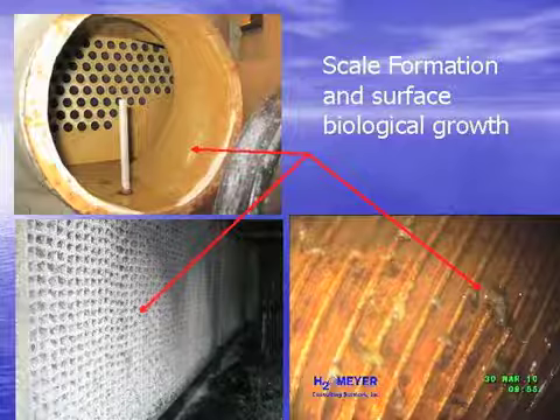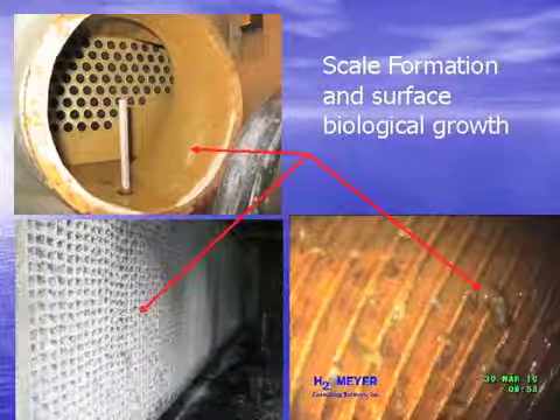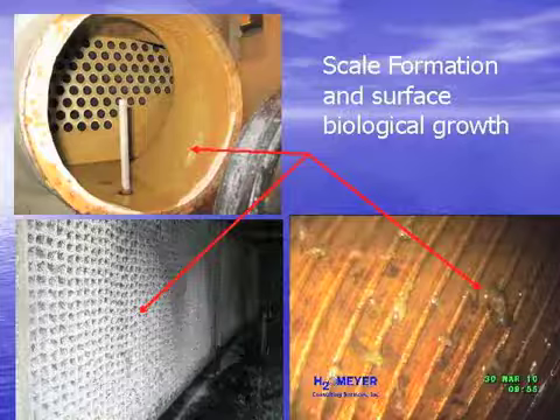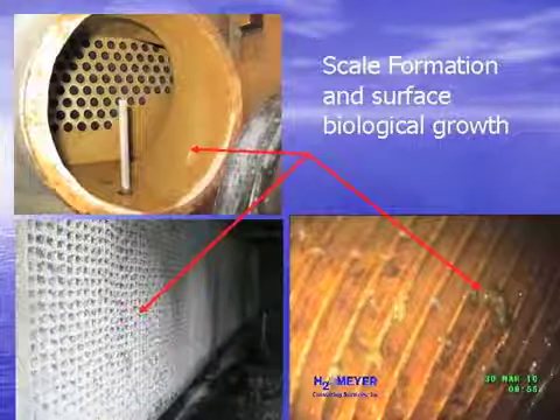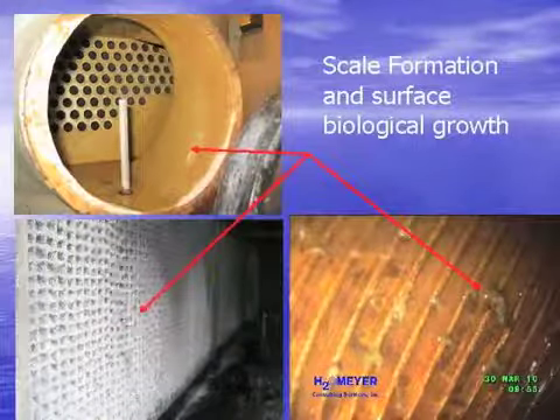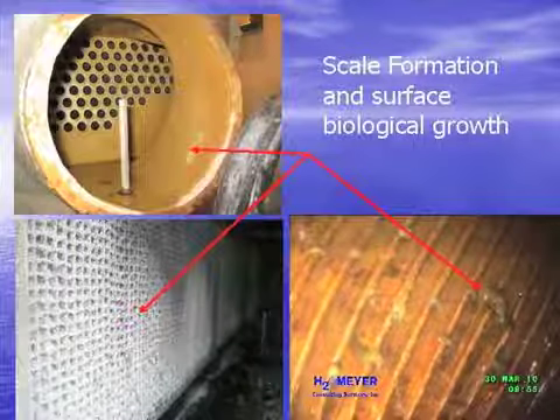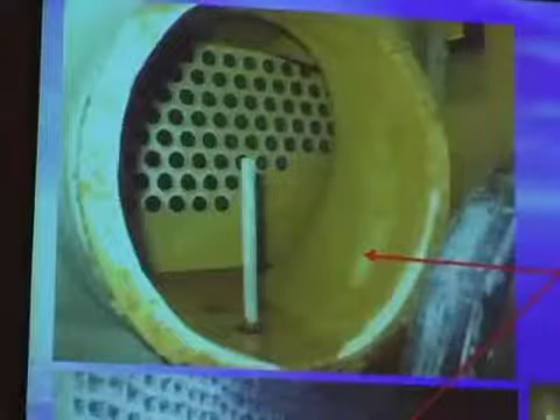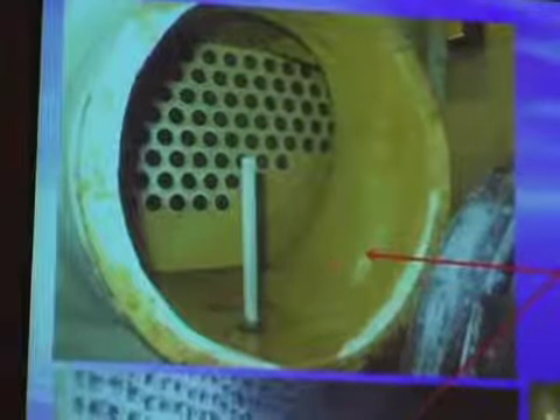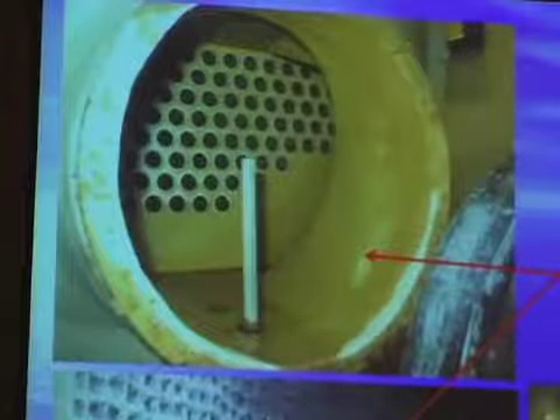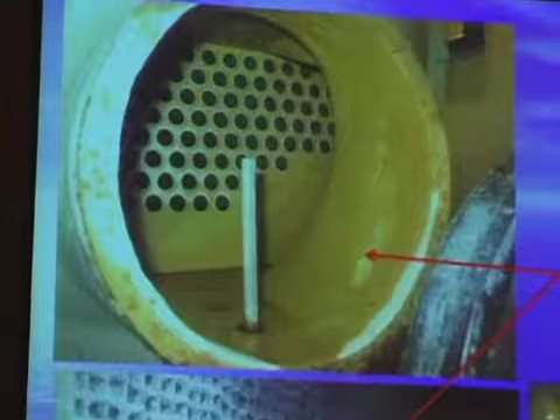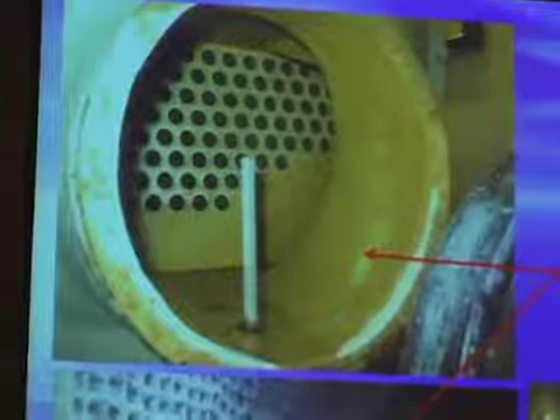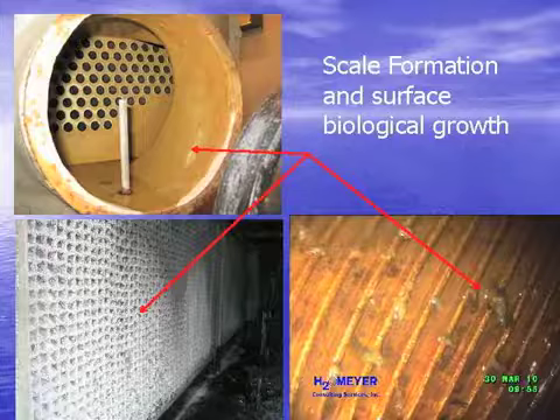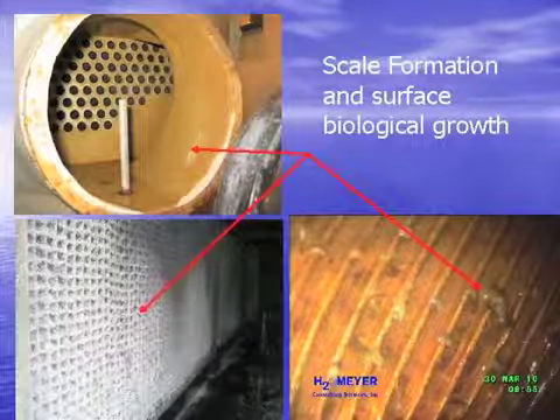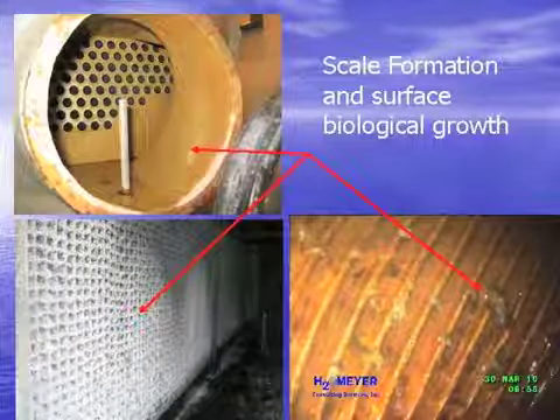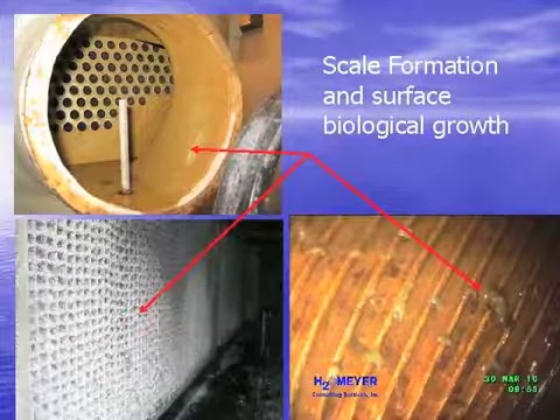When we've actually taken a look at some of the equipment after it's been inspected, we see this is basically a header box of the condenser. We pulled the end bells off, so you can see the head box right there. By the way, this is a gray epoxy-coated tube sheet. If you notice the color, it's not gray. This is all the biological fouling that we've seen in the tube sheets. If you look at some of the borescope pictures on the tube sheets, we actually see biological growth growing on the tube surfaces themselves, which obviously causes pitting underneath those tubes and is going to cause some damage.